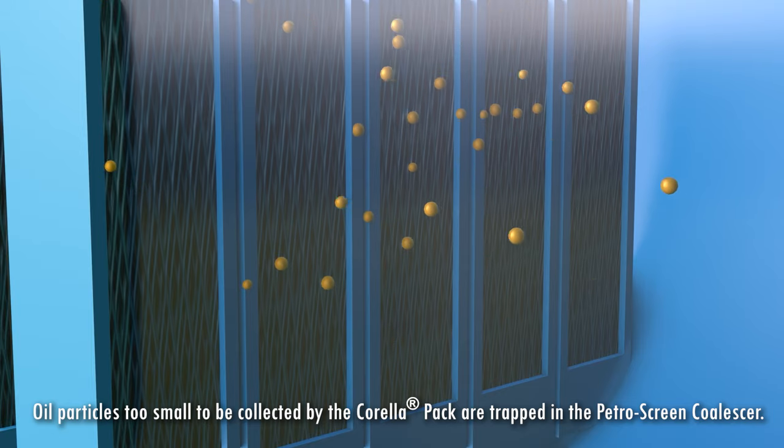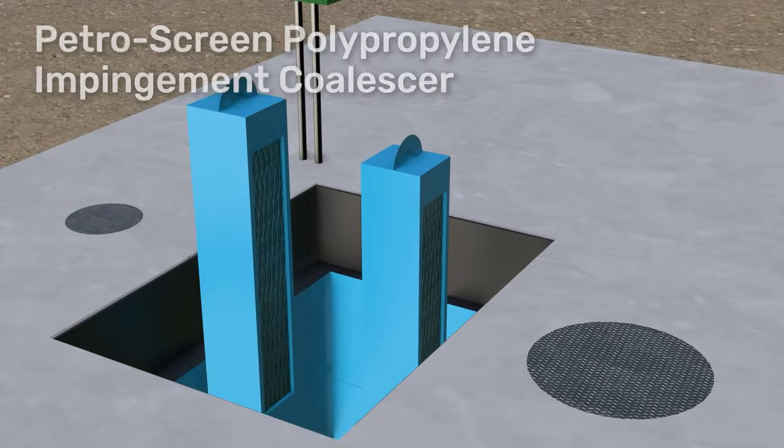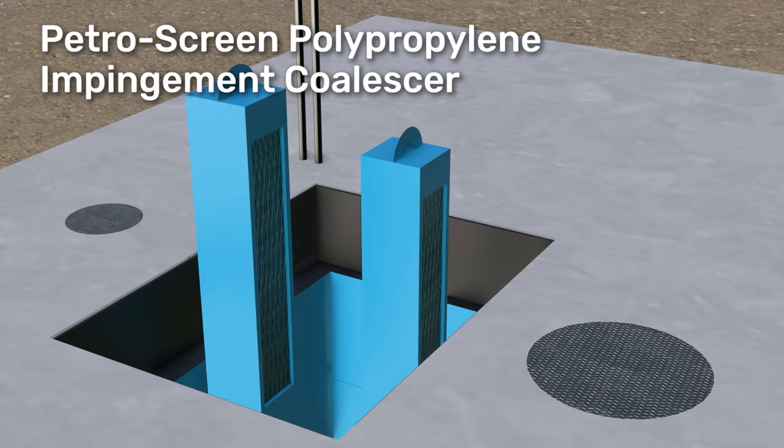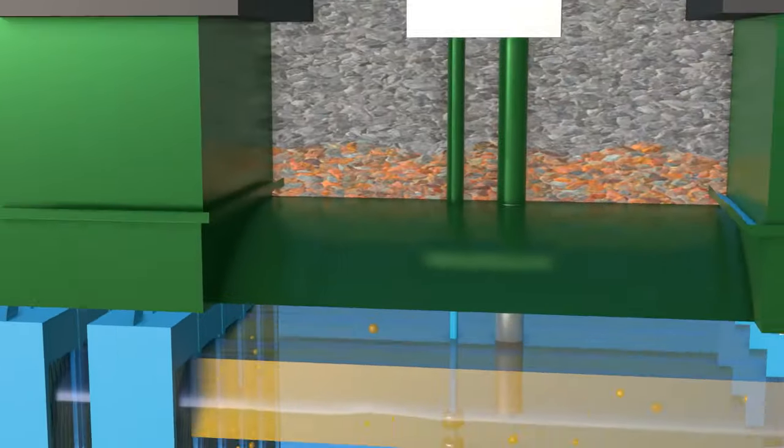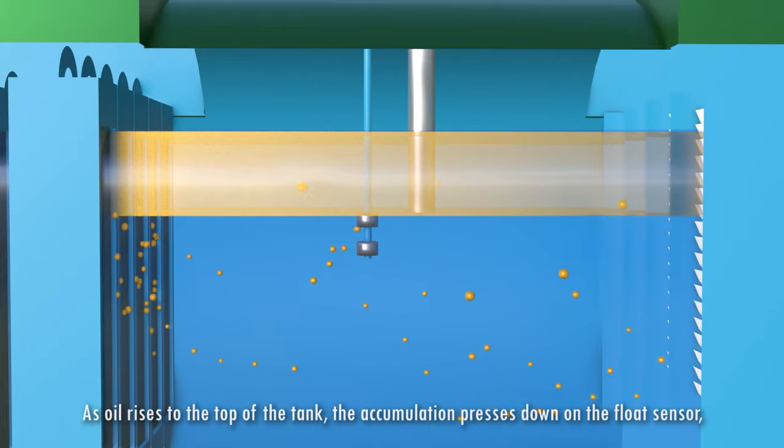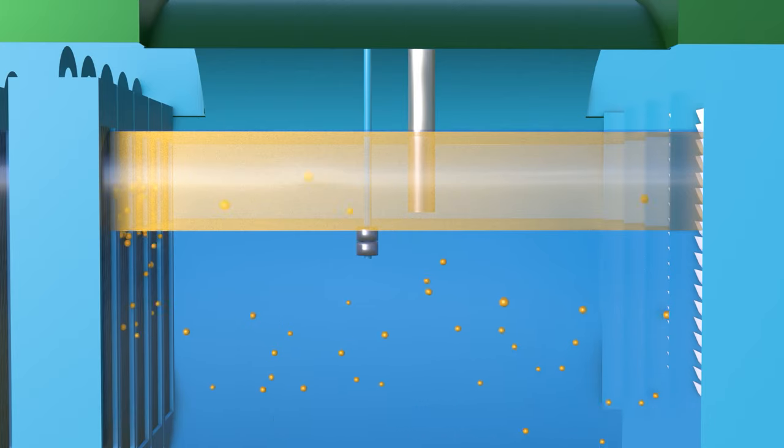Now those also can be removed through an easy access rectangular manway that we're showing for inspection and clean out. As we're accumulating oil on top of the water, we're flowing through the vessel and as the oil builds up on top of the water it sinks the top float which sounds an alarm on our control panel.